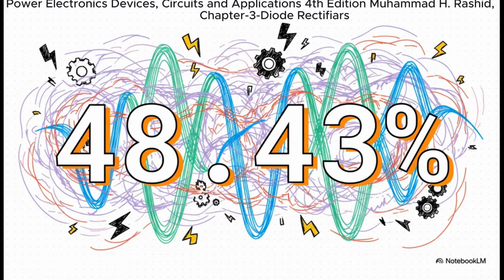48.43%. That is a huge amount of distortion. It means there's almost half as much energy sloshing around in those useless, noisy harmonics as there is in the fundamental frequency we actually want. This isn't just a number - this is a measure of the electrical noise this one device is injecting back into the power grid.